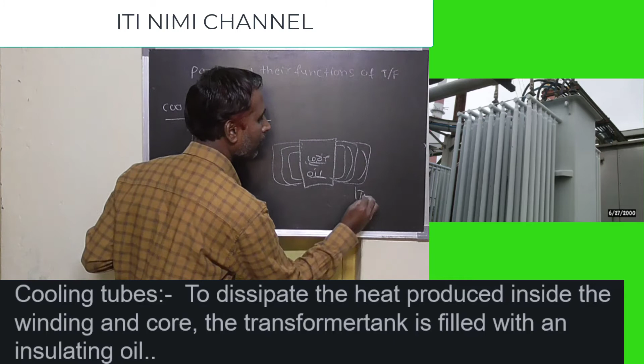...exposed to natural air. The tubes are put outside, in the fresh air - this is not the inside part, this is the outside part. The tubes are put in the atmosphere or natural air, that's why the cooling tubes cool the heated transformer oil.